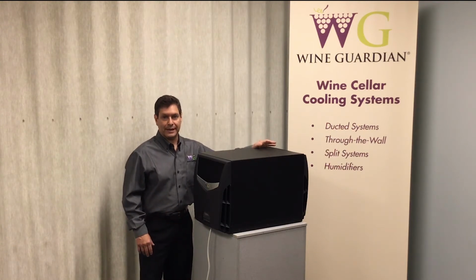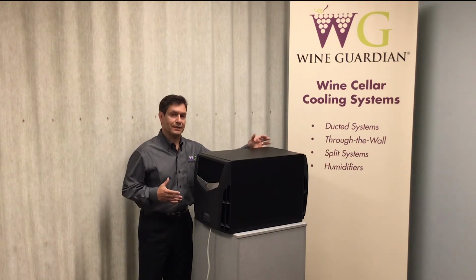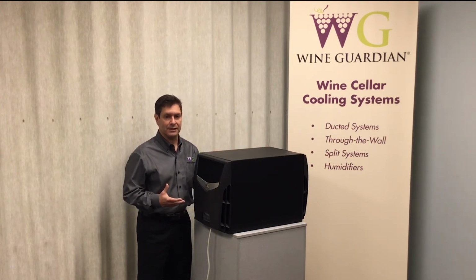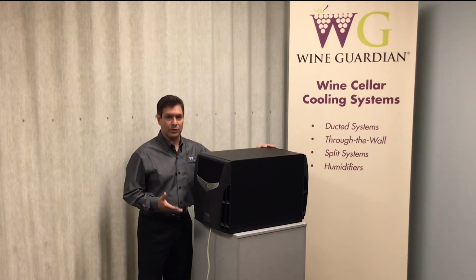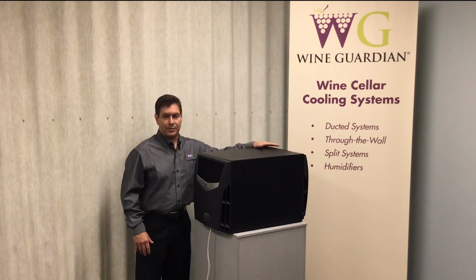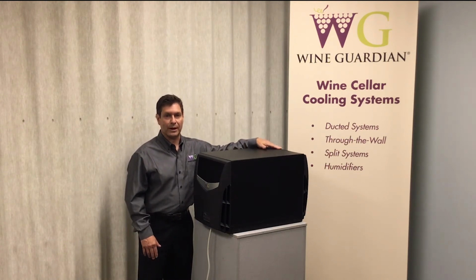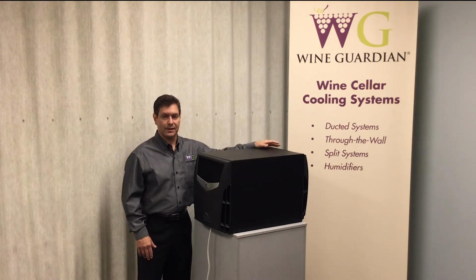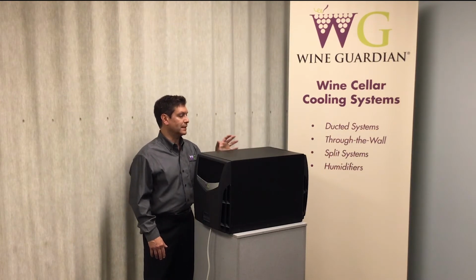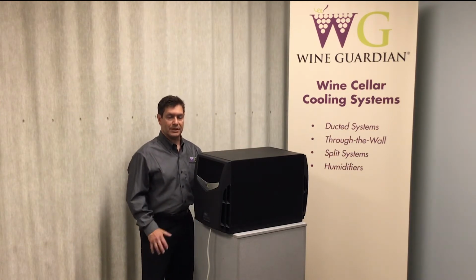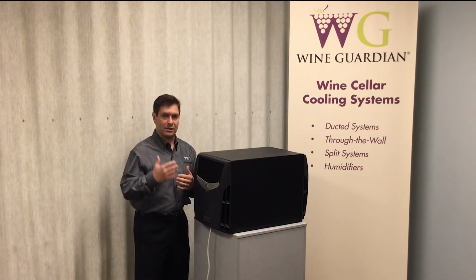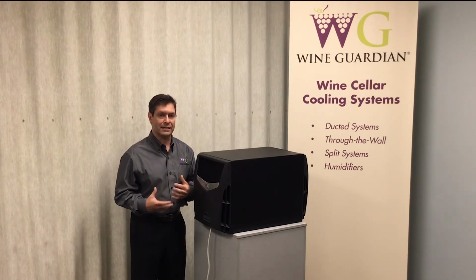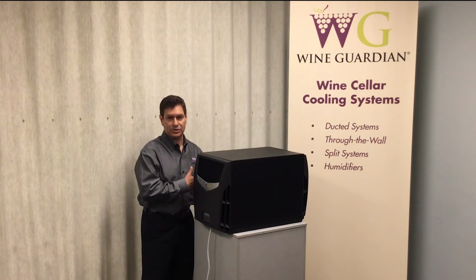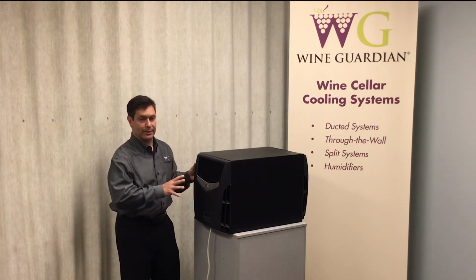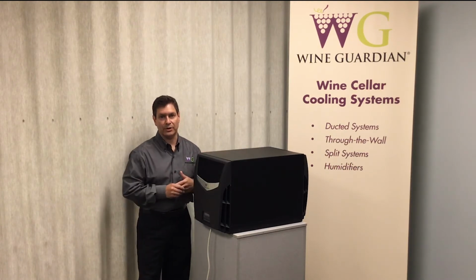The venting area has to be able to breathe. You can't just put this in a closet with no airflow surrounding it or ability to bring in air to this unit and expect it to work. It will not happen and will not work efficiently, and you'll end up with problems. We recommend that the venting area be at least 2.5 to 3 times the size of your wine cellar for proper operation, proper heat dissipation out into the space. Having said that, we have had units mounted in closets or very small areas, but the venting is accommodated by exhausting the hot air out or by bringing fresh air into that space so the unit can effectively breathe on the condenser side. So you should be aware of how this is being mounted and how the condenser side is going to breathe.